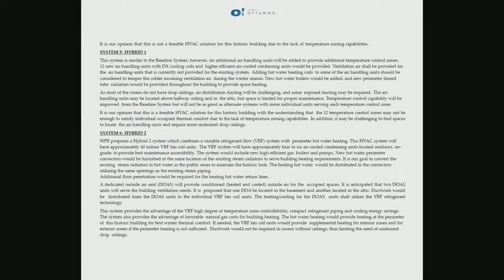We proposed hybrid 2, a system with small concealed fan coils in each room running off refrigerant electric, combined with a perimeter heating system. We can have a hot water boiler, natural gas, replace the radiators with hot water, and in historic cases retrofit them to run hot water, or provide a different radiator that still looks historic but functions with hot water. For office tenants we wouldn't try to reuse the old radiators since some are bad and blanked off anyway.